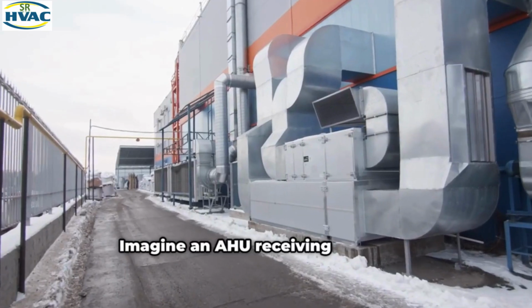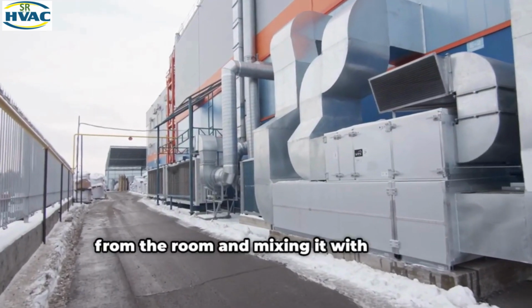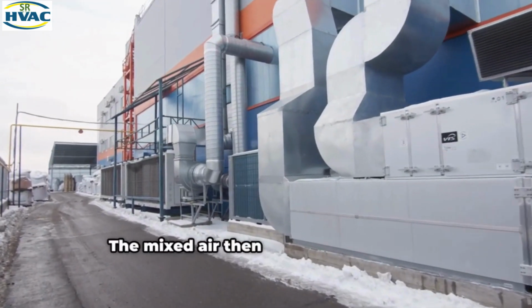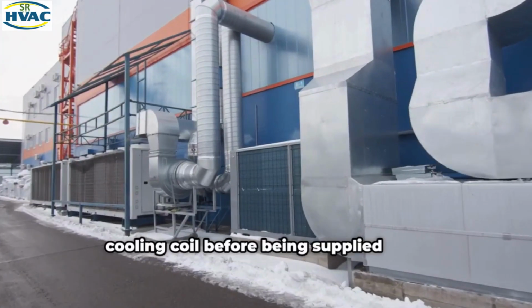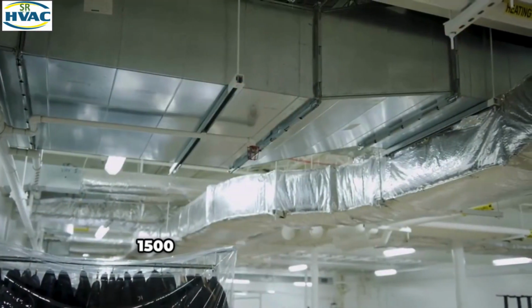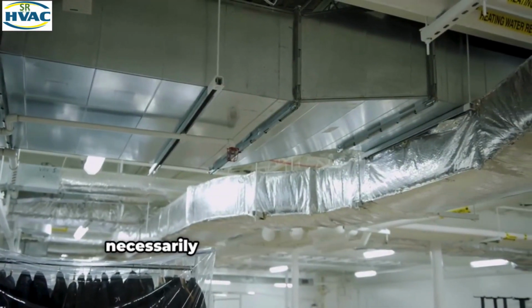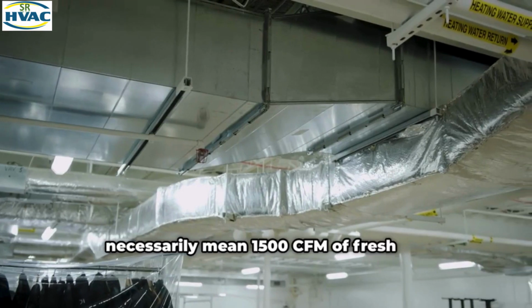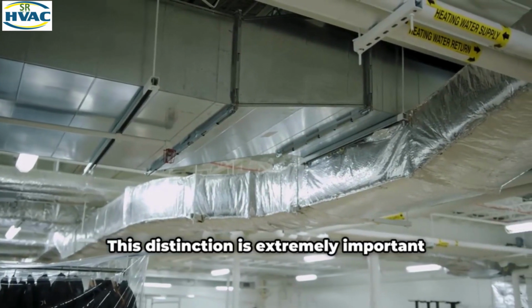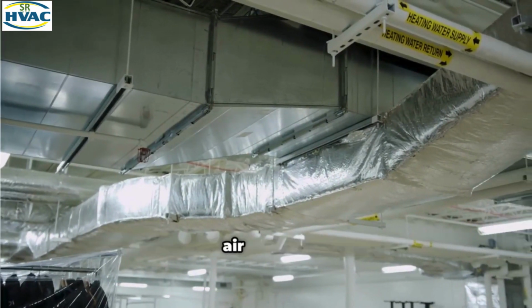Imagine an AHU receiving return air from the room and mixing it with outdoor fresh air. The mixed air then passes through the cooling coil before being supplied back into the room. Therefore, 1500 CFM of supply air does not necessarily mean 1500 CFM of fresh air. This distinction is extremely important when discussing ventilation and indoor air quality.